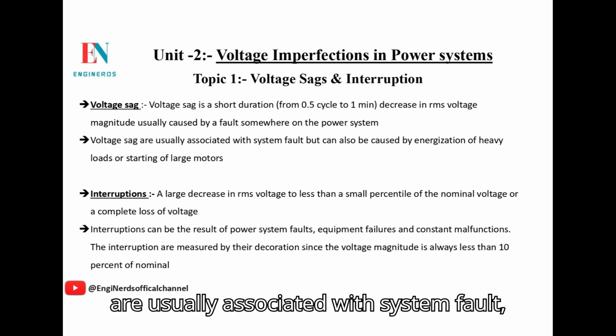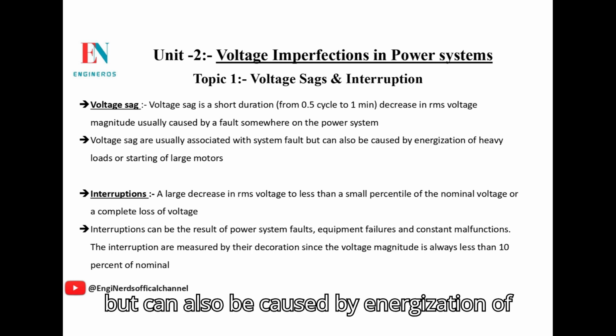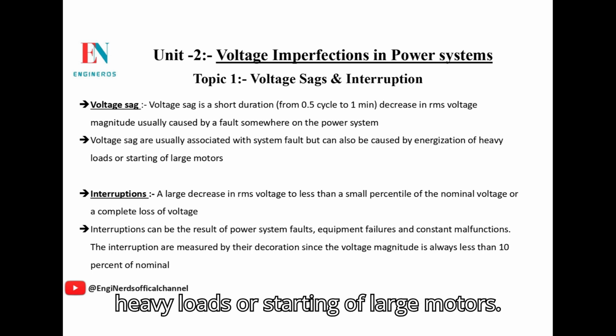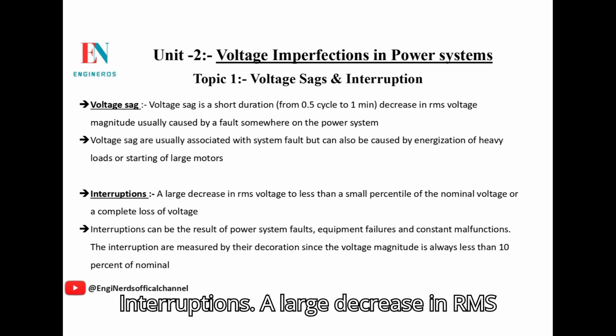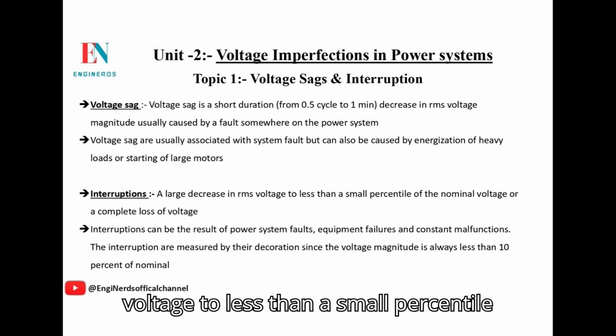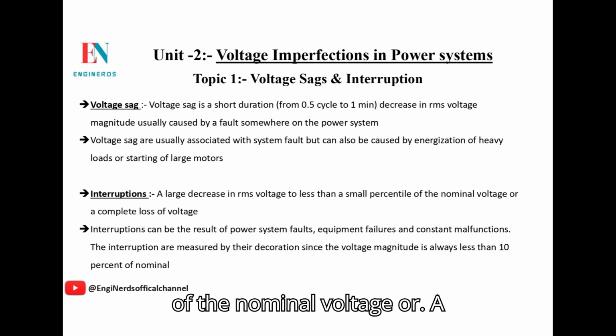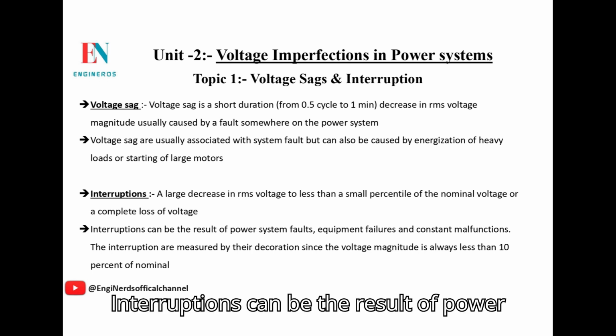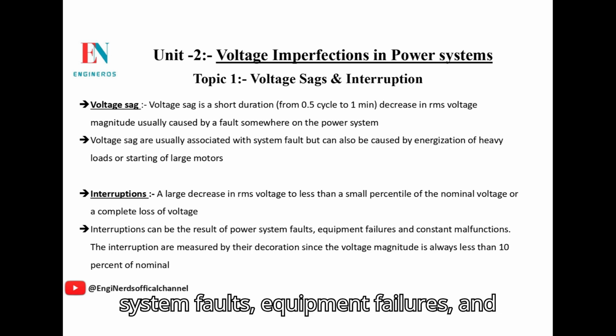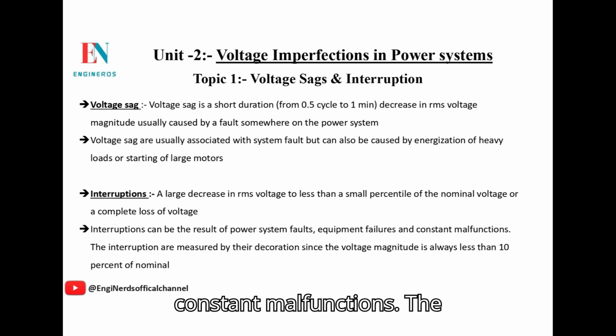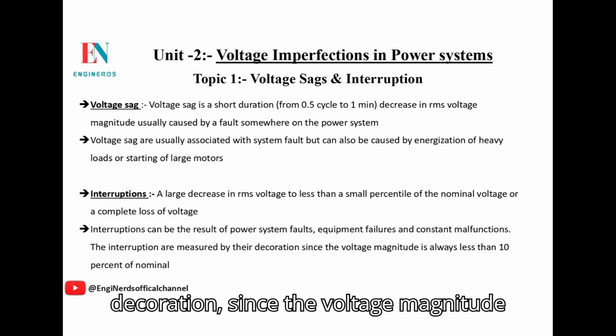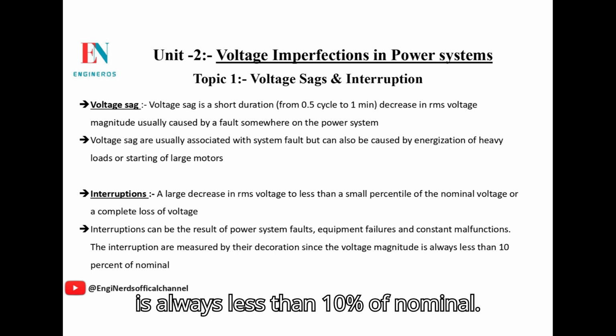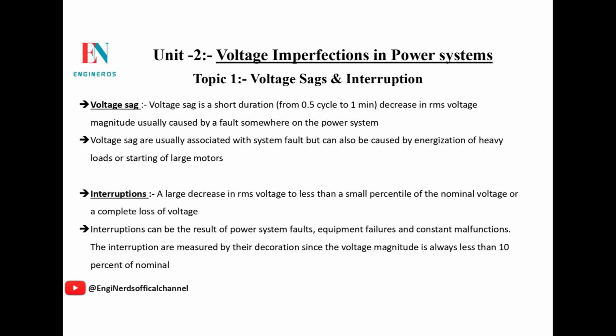Voltage sags are usually associated with system faults but can also be caused by energization of heavy loads or starting of large motors. Interruption is a large decrease in RMS voltage to less than a small percentage of the nominal voltage, or a complete loss of voltage. Interruptions can be the result of power system faults, equipment failures, and control malfunctions. Interruptions are measured by their duration, since the voltage magnitude is always less than 10% of nominal.